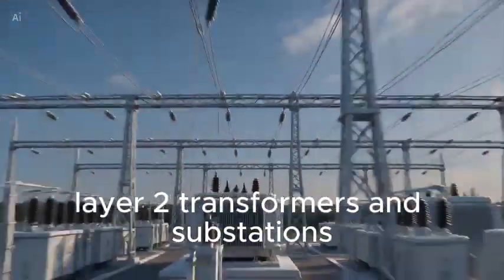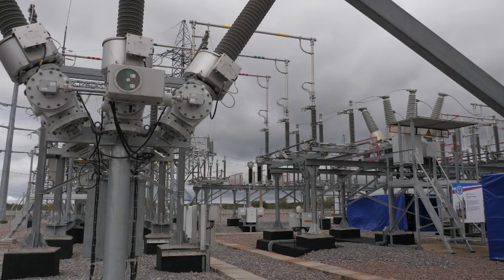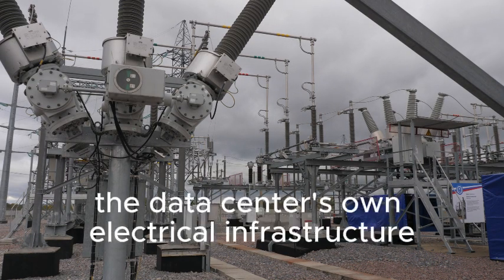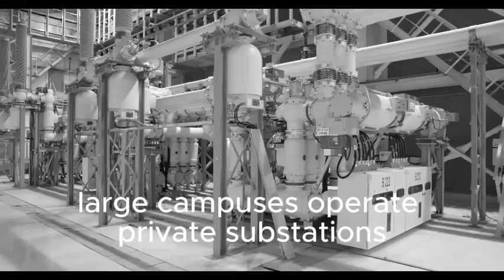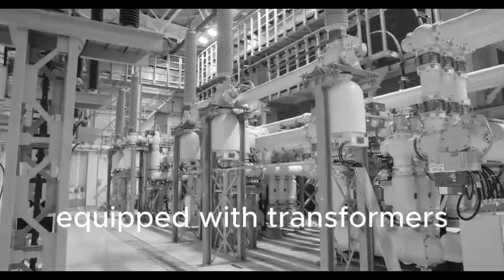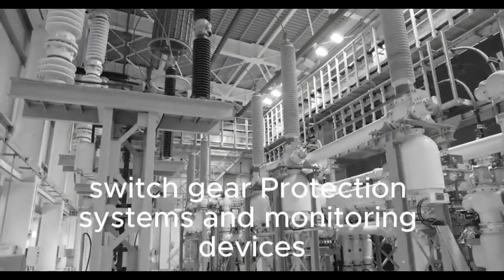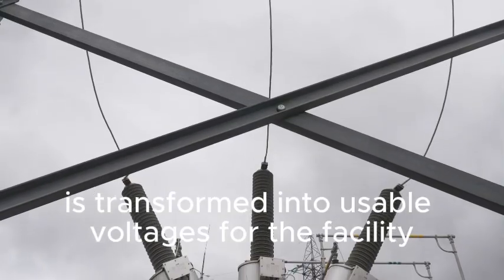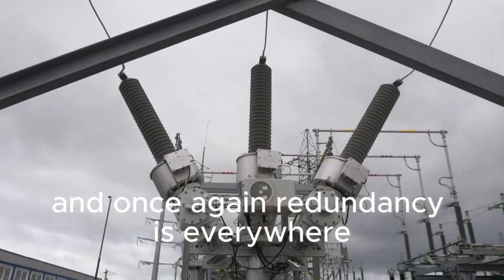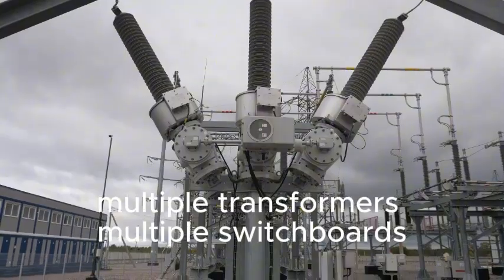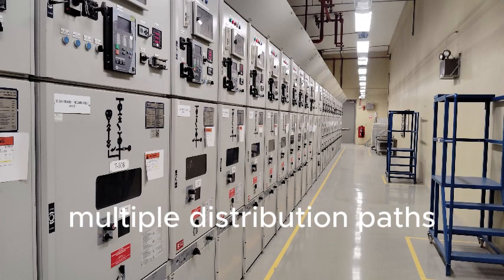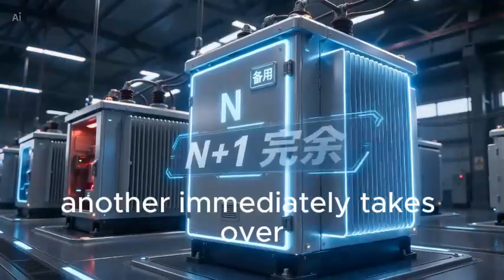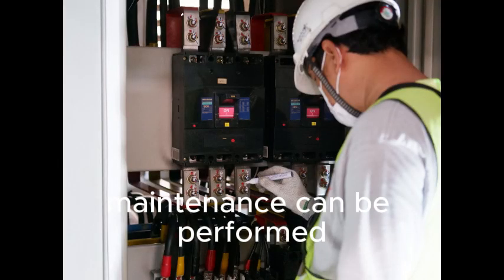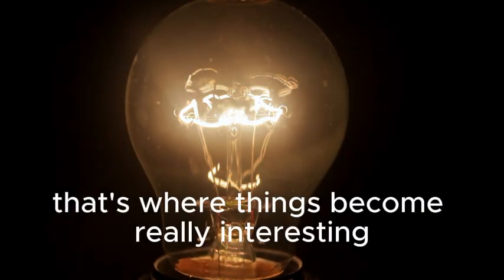Layer 2. Transformers and substations. Once electricity arrives on site, it enters the data center's own electrical infrastructure. Large campuses operate private substations equipped with transformers, switchgear, protection systems, and monitoring devices. High-voltage electricity is transformed into usable voltages for the facility. And once again, redundancy is everywhere. Multiple transformers, multiple switchboards, multiple distribution paths. This design philosophy is called N+1 redundancy. If one transformer fails, another immediately takes over. Maintenance can be performed without shutting down operations. But what happens if the entire utility grid disappears? That's where things become really interesting.